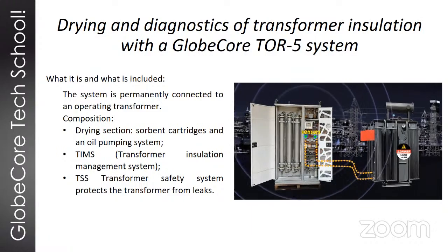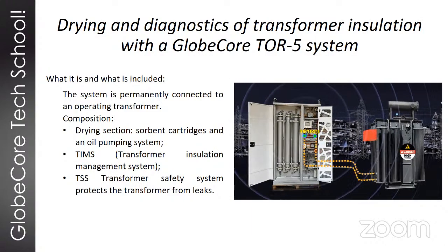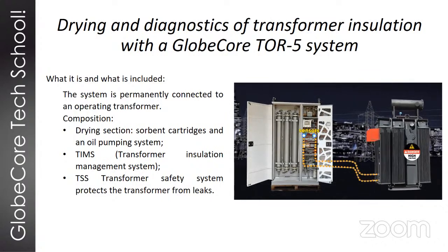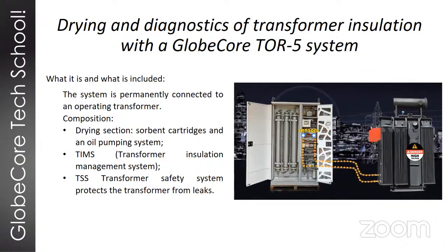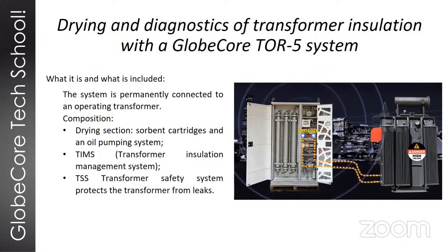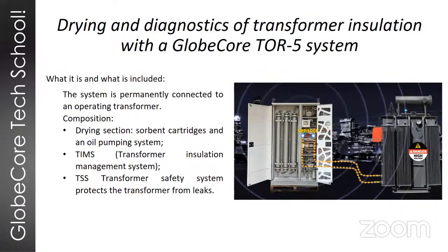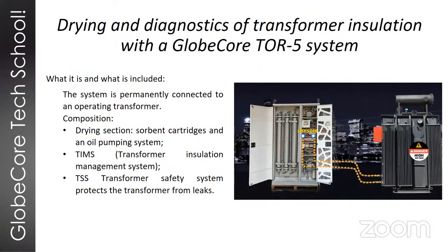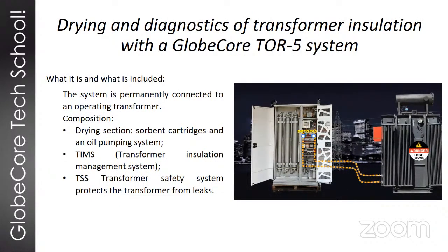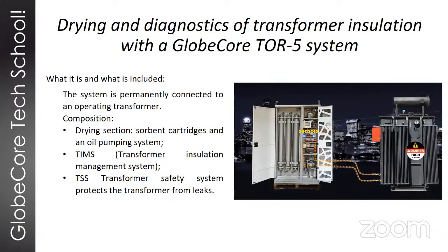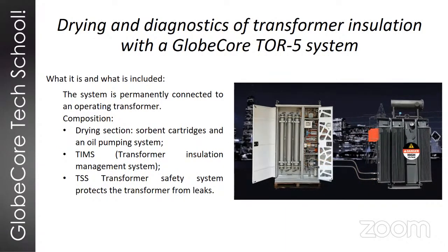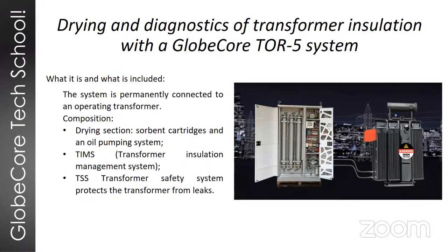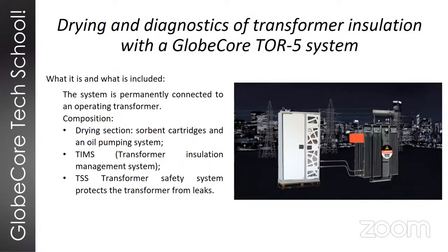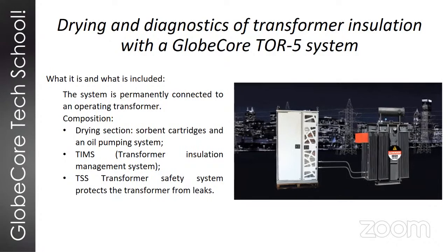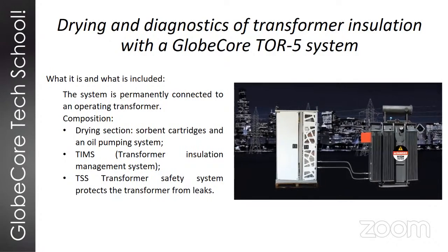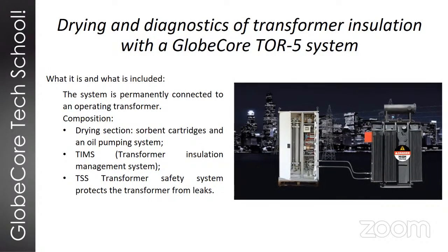So as the water, as I've said several times, in the transformer migrates from vapor into oil and back, such circulation through absorbers allows us to remove water not only from the oil, but also from insulation, slowly and over time. So using a TOR5 system on a transformer over the entire lifetime of the transformer makes sure the transformer is basically always kept dry. The next section that we have here is a monitoring and data collection system, the TIMS, Transformer Insulation Management System.